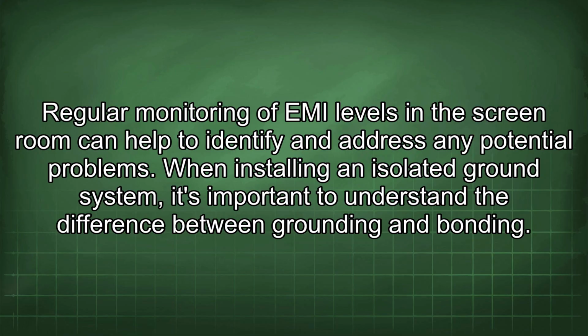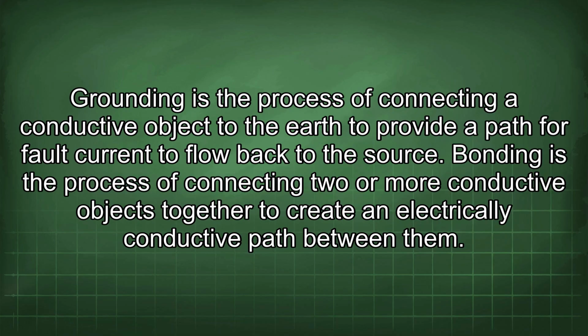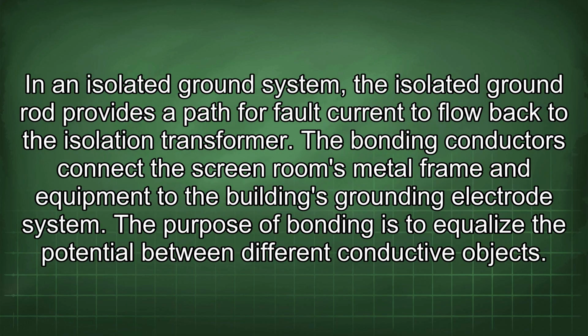When installing an isolated ground system, it's important to understand the difference between grounding and bonding. Grounding is the process of connecting a conductive object to the earth to provide a path for fault current to flow back to the source. Bonding is the process of connecting two or more conductive objects together to create an electrically conductive path between them. In an isolated ground system, the isolated ground rod provides a path for fault current to flow back to the isolation transformer. The bonding conductors connect the screen room's metal frame and equipment to the building's grounding electrode system.